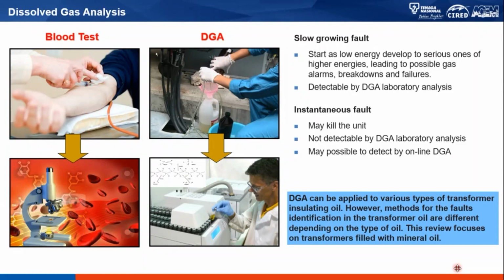We know that DGA is very useful for slow growing fault, meaning that there is a fault growing inside the transformer that we can monitor, and we can do a trending of the gases that is produced due to the decomposition of oil or perhaps the paper insulation.